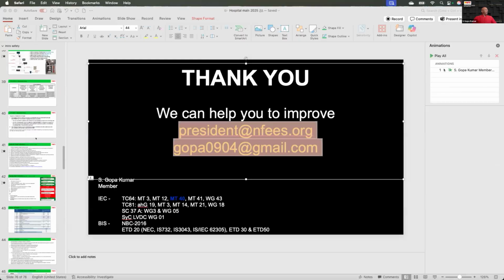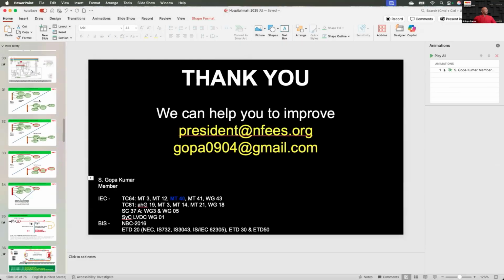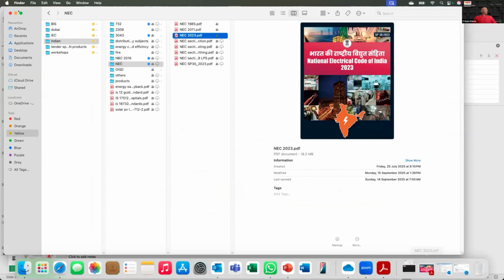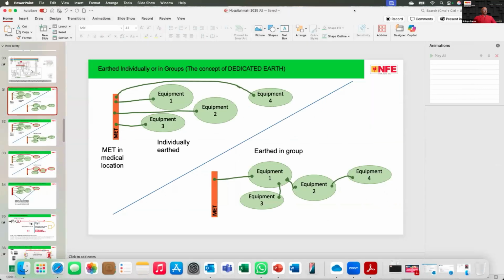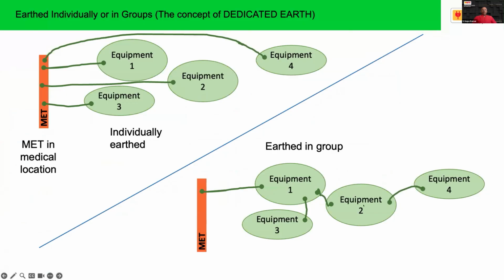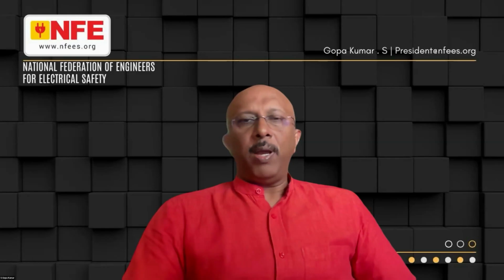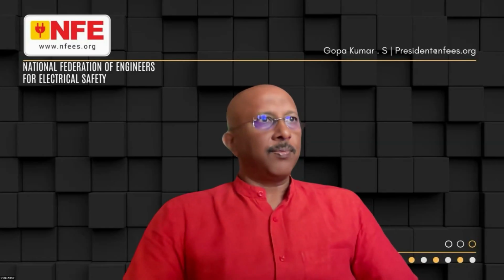Now, I have shown one of the pictures. Let me take that picture. I'm sure you are able to see the screen. Now, on the top where I am moving the cursor, this is called individually dedicated earth. For example, an individually earthed system means each of the equipment must be connected to the common earth bus bar in the room separately. And the bottom is connected in group. Biomedical equipment, most often, you cannot earth in groups. You have to individually earth. Hope it's clear. You can find this picture in the standards as well.